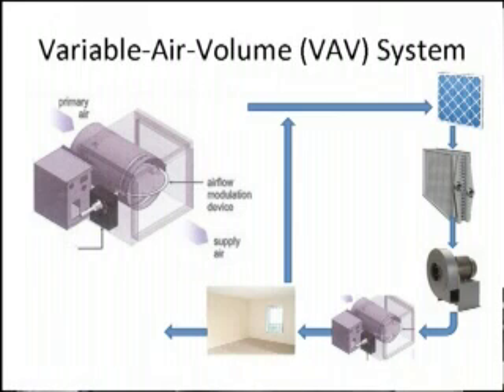We're trying to reduce its airflow to as low as we can while maintaining the ventilation rates. When we back that down, this guy automatically backs down because he's got a feedback with the pressure in the duct. So as this box starts to close down because we've lowered the CFM, then this guy backs down. When that guy backs down, then the cooling load backs down on the cooling coil, and that translates back to the refrigeration side, and it starts backing that down. So instead of starting, as a lot of people do, with the chillers or the compressors, I like to start at the other end of the equation and try to optimize in the reverse order, and that's been real successful for us.